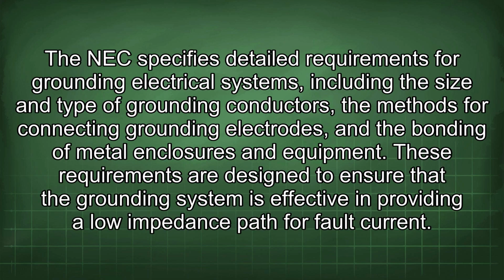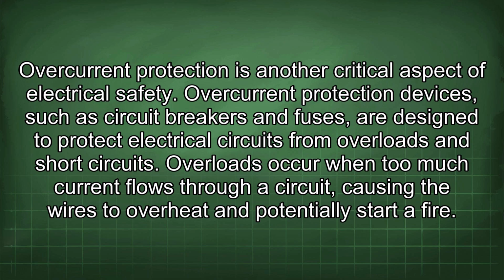The NEC specifies detailed requirements for grounding electrical systems, including the size and type of grounding conductors, the methods for connecting grounding electrodes, and the bonding of metal enclosures and equipment. These requirements are designed to ensure that the grounding system is effective in providing a low impedance path for fault current. Overcurrent protection is another critical aspect of electrical safety.